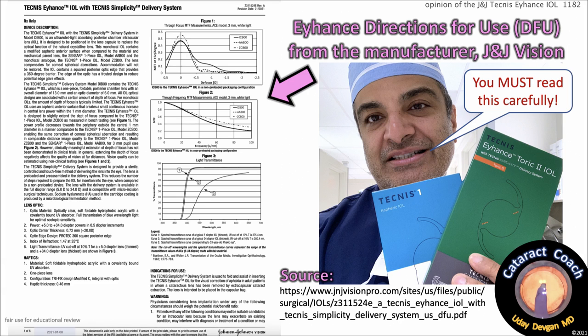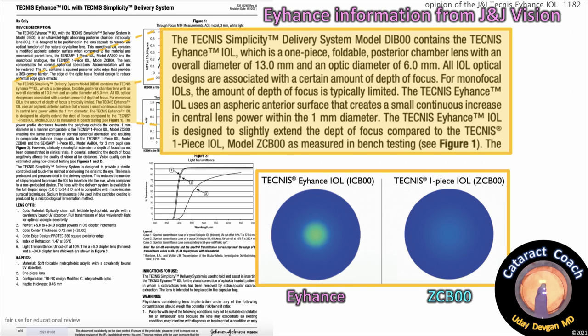Here's the source where you can download it yourself online. One section says the TECNIS Simplicity Delivery System, model DI-B00, contains the TECNIS Eyehance IOL, which is a one-piece foldable posterior chamber lens with an overall diameter of 13mm and an optic of 6mm. All optical IOL designs are associated with a certain amount of depth of focus. For monofocal IOLs, that depth of focus is typically limited. The TECNIS Eyehance IOL uses an aspheric anterior surface that creates a small, continuous increase in central lens power within the central 1mm diameter.